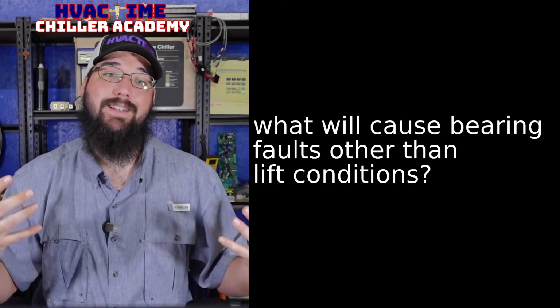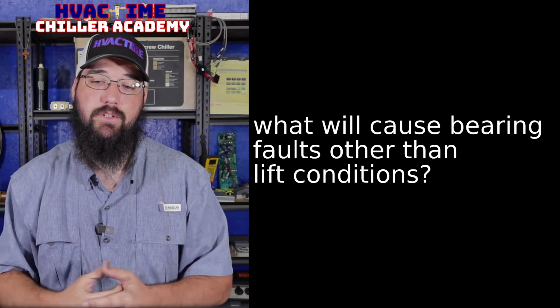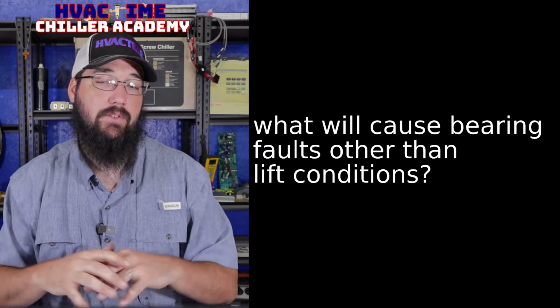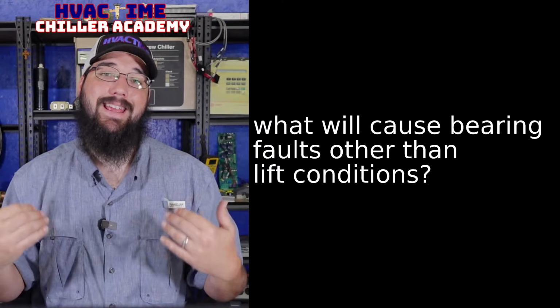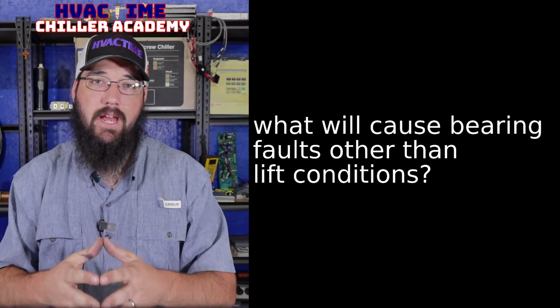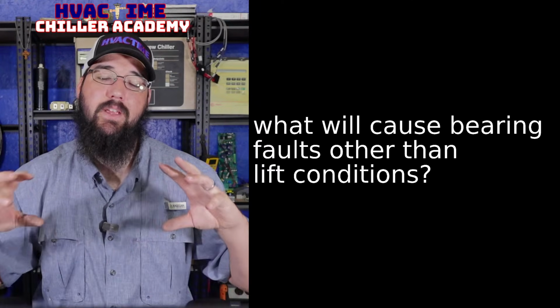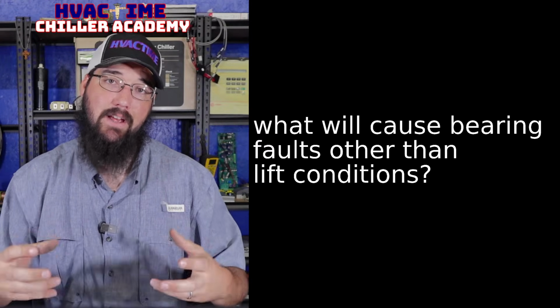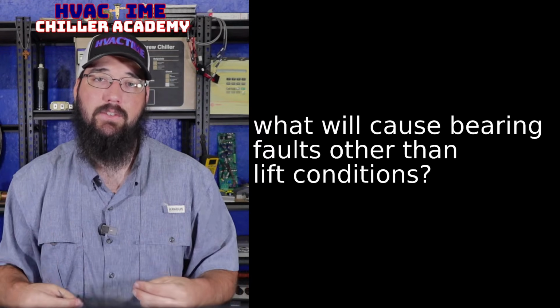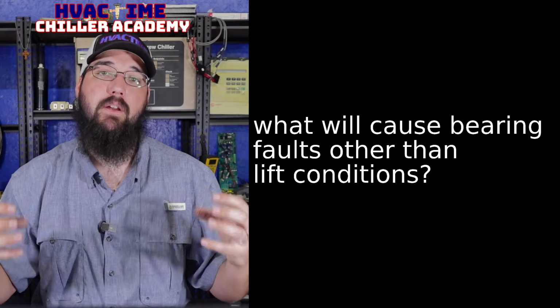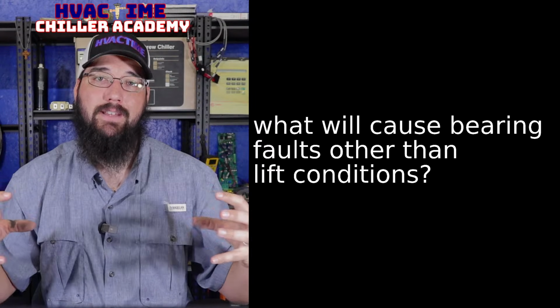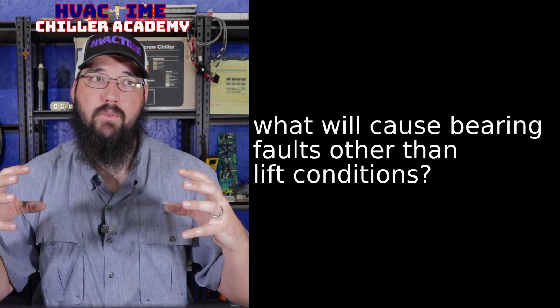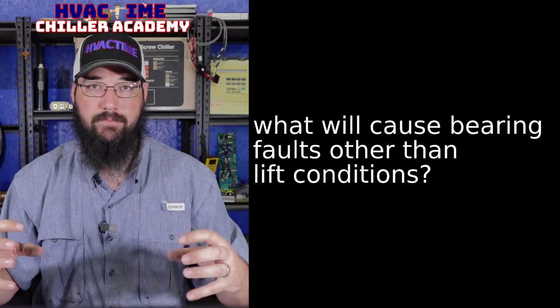Or we could have a demag situation, which is a demagnetized shaft. Now, these are not very common, but they can happen. So the shaft in a Turbocor specifically is a permanent magnet shaft. And as that shaft demagnetizes, it will affect the bearing's ability to maintain the orbit of the shaft.